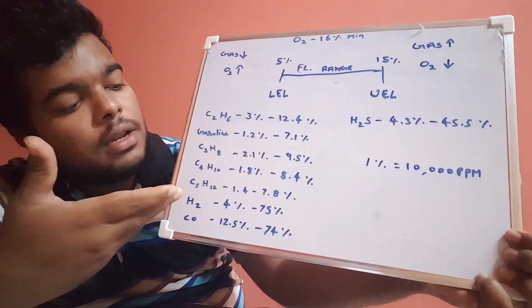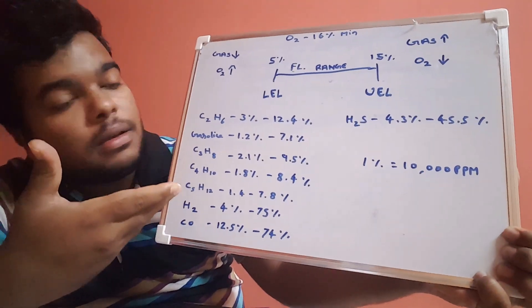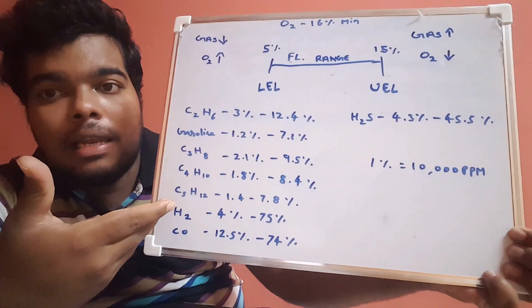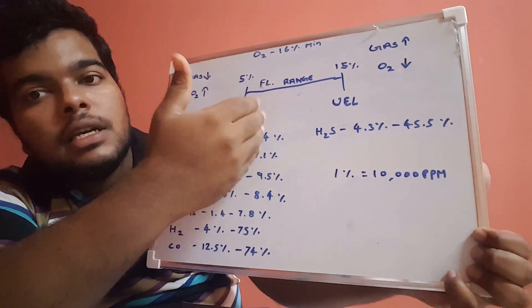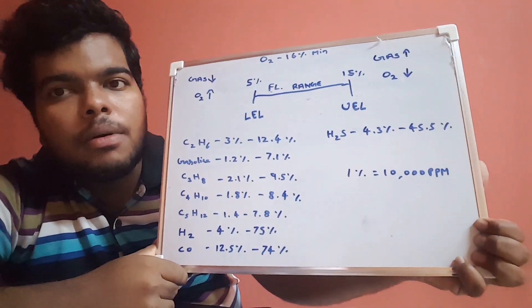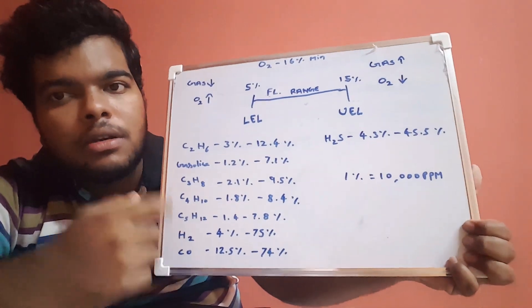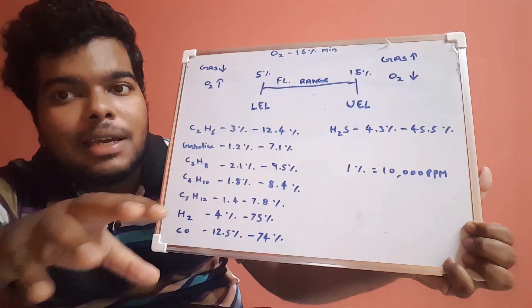I have also given some of the values of oil and gas gases and all these values of LEL and UEL which you can see. Actually, CH4 is methane, which already has 5 to 15 percentage. It's already given in our multi-gas detector. This is the range of the multi-gas detector which is calibrated for the quantity of methane in the air.